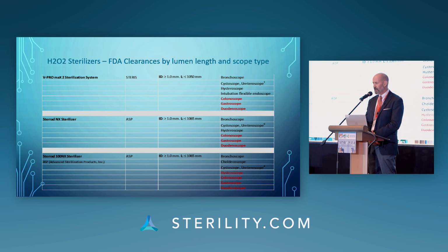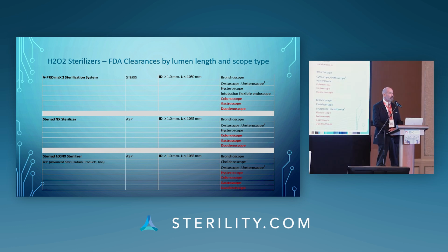This spreadsheet shows 3 of the most popular hydrogen peroxide systems in the United States and their FDA clearances. And as you see, these systems have been cleared for a range of shorter scopes, bronchoscopes, cystoscopes, ureteroscopes. They have not been cleared for duodenoscopes, for gastroscopes, for long colonoscopes. There are a number of technical reasons for this, but these systems are not appropriate for the longer scopes that we've been discussing.